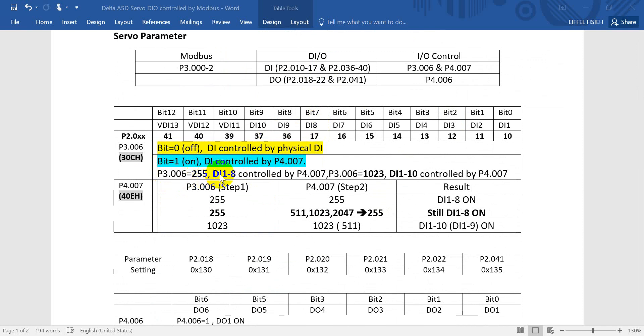So for example, if we want to control digital inputs DI1 to DI8, we have to set all those bits on. So if we define P3-006 equal to 255, that means DI1 to DI8 will be controlled by P4-007. And if we define P3-006 equal to 1023, then that will include DI9 and virtual DI10. Here I will show you the sequence: first we define the value in P3-006, then we give the value in P4-007, and then we can see the results.